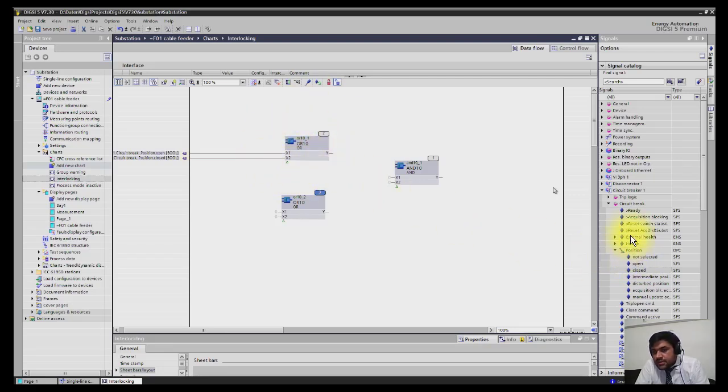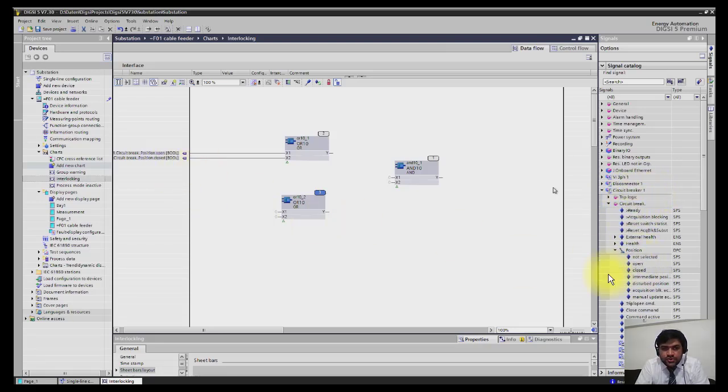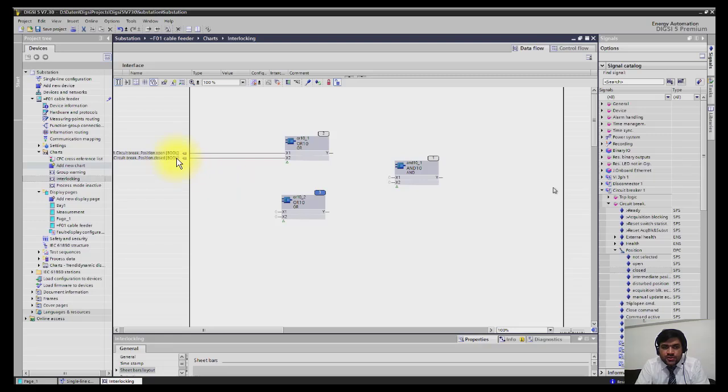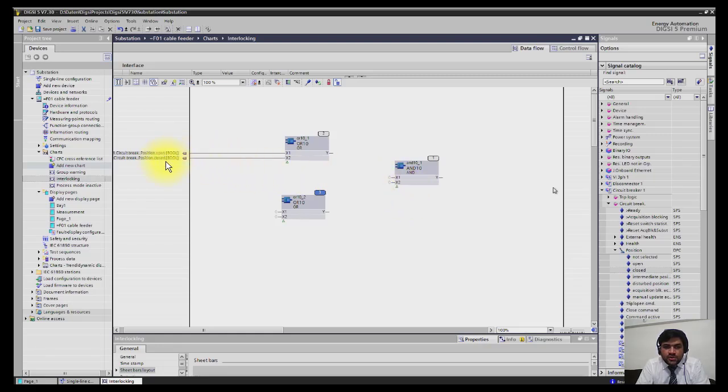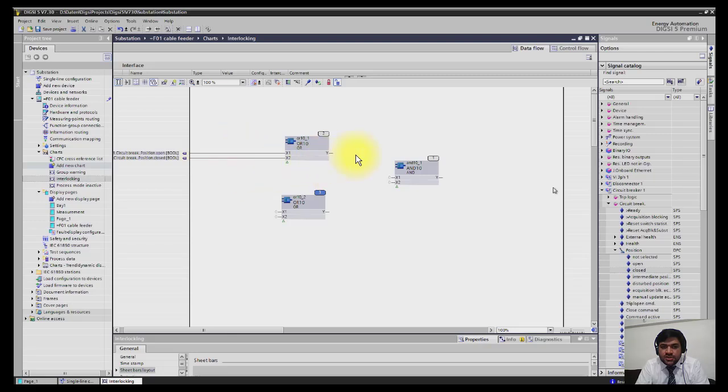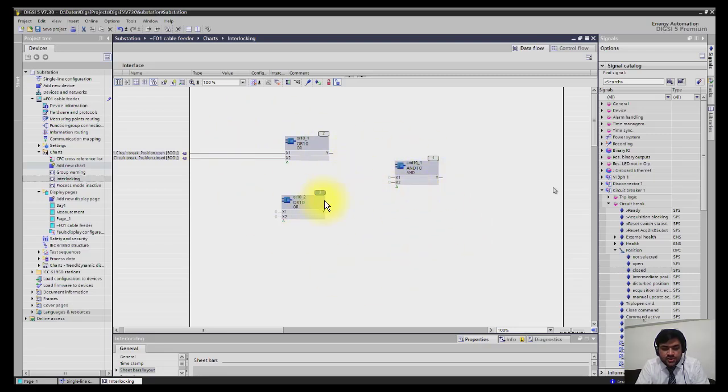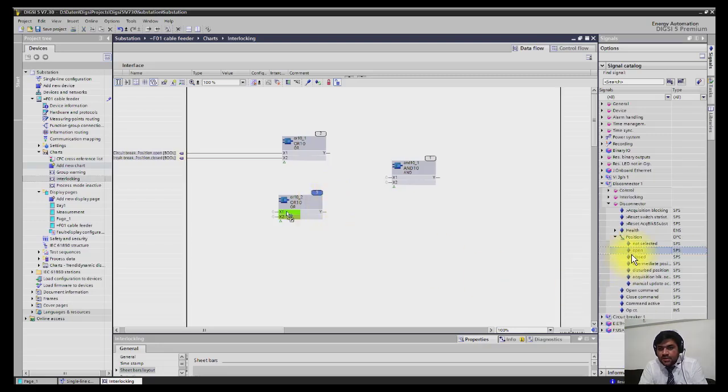Now I will select first the inputs for the isolator. For the breaker first of all I will select, I have selected open position, drag and drop here, and then close position, drag and drop here and connect to x1 and x2. So if breaker is open it will be one here at output because it's OR gate will be connected here. So if breaker is closed it will be one here. If breaker is neither open nor close, no output is coming, it's an intermediate position, then there will be zero and breaker output is not one so you can't operate the breaker. So this is how you are building the logics in the charts.